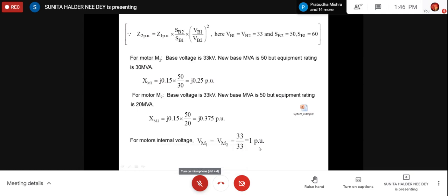Why? Because generally we calculate this reactance diagram for fault calculation. And in fault calculation, that means an abnormal condition, the sources will contribute to the current. Now an induction motor does not behave as a source, it has no internal excitation, but if there is a synchronous motor, then it has an induced EMF and it can send current in the reverse direction. So it will act as a source of current when there is a fault.